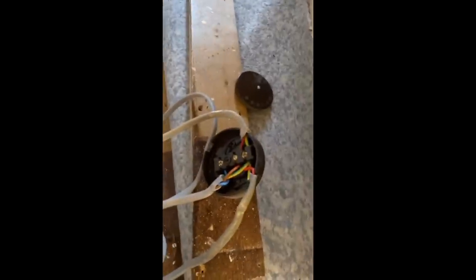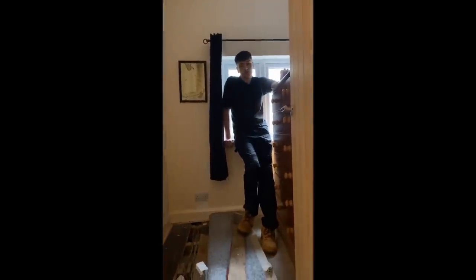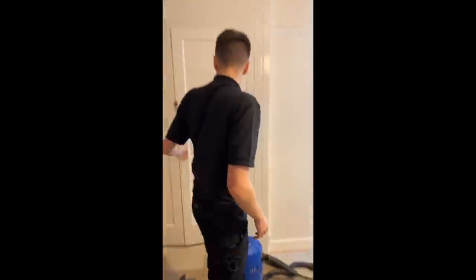Bye. Now when you start a job, and you wish you hadn't even bothered coming to work today. Shockingly bad. James, did you do this? So we're walking off this job. We're not walking off, not bad intentions. We can't do anything today. So we've ripped out all these sockets that are completely wired crap. James is going to hoover up. I've reinstated this circuit that still is spurs off of spurs off of spurs off of spurs, but you can't leave the client with no power.